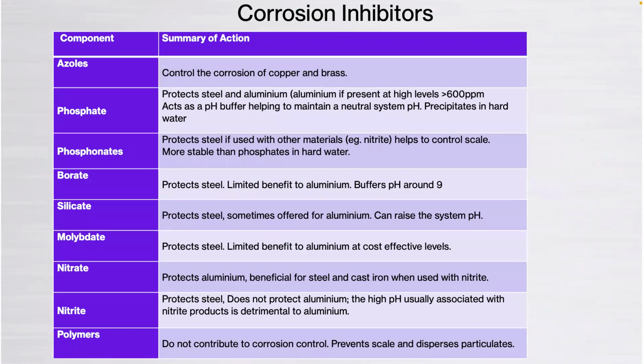There are different types of inhibitors. Don't expect we need to know all of these, but just be aware there are different types of inhibitors that do various roles to protect different metals in the system. So you'll have all kinds of blends of products out there available. But just because someone says it's an inhibitor, it's great, it's an inhibitor, I do recommend that if you can specify a product, it should at least have NSF approval. So whether that's a glycol or an inhibited glycol, some form of kite mark that says it's been independently verified.